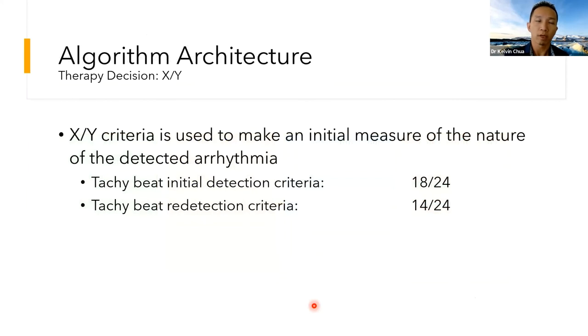For this X over Y criteria, the nominal setting for the SICD is 18 out of 24, which means this is a running rolling window, similar to some of our transvenous algorithms. There's a rolling window of 24 beats, and out of these 24 beats, if 18 of them satisfy tachy criteria in terms of intervals, this will satisfy the tachy detection.